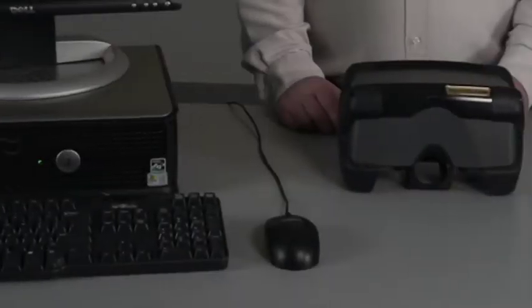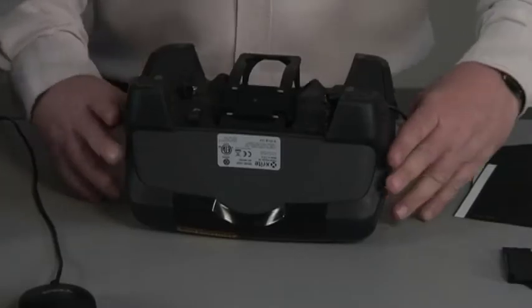Now that we have everything out of the box, let's connect the instrument to the computer. First thing we want to do is connect the power to the instrument. We want to have the instrument power up for at least 30 minutes. That warms the instrument up and makes it so it's acclimated to the conditions in your paint store.